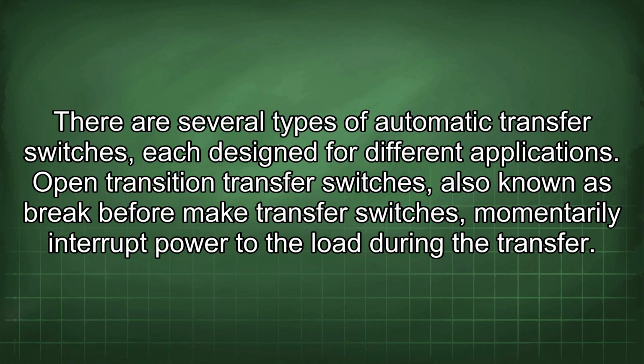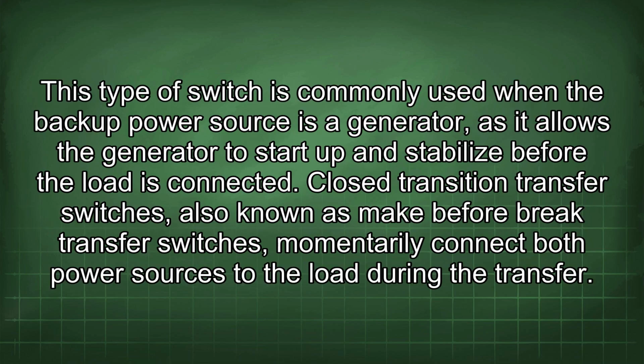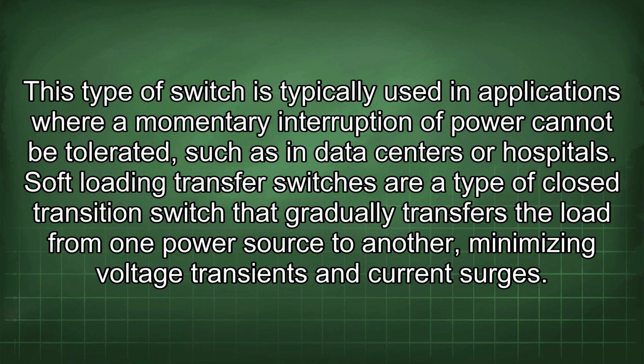There are several types of automatic transfer switches, each designed for different applications. Open transition transfer switches, also known as break-before-make transfer switches, momentarily interrupt power to the load during the transfer. This type of switch is commonly used when the backup power source is a generator, as it allows the generator to start up and stabilize before the load is connected. Closed transition transfer switches, also known as make-before-break transfer switches, momentarily connect both power sources to the load during the transfer. This type of switch is typically used in applications where a momentary interruption of power cannot be tolerated, such as in data centers or hospitals.